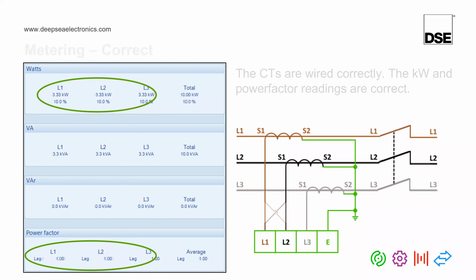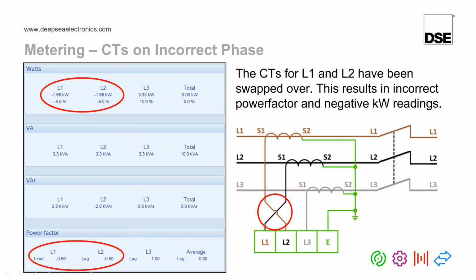However, in the next example, for some reason, the connections have been swapped over on the back of the DSE module. So the L1 CT has been wired to L2, and the L2 CT has been wired to L1. The first thing we need to check here is power factors. Whenever doing step number 2, the first thing you should always check is whether the power factors are correct. In this example, even though we are powering a purely resistive load, the same load that was just shown in the previous example, we have incorrect power factors. This incorrect power factor is caused by L1 and L2 being swapped over. But in the same vein, you can also see that the kilowatts are being shown incorrectly. This is why we always check the power factors, because if the power factors are wrong, this fault causes two issues: incorrect power factors and incorrect kilowatt readings.